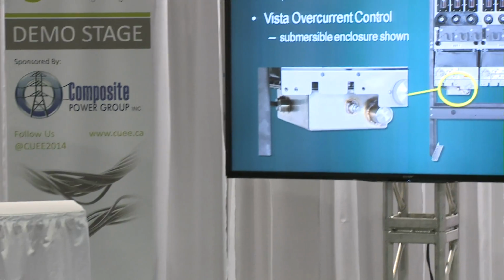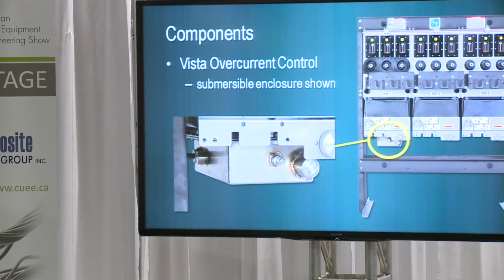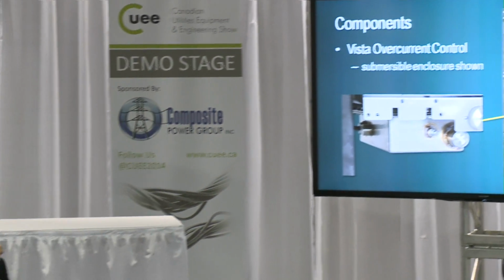If it's a fault interrupter, you get current transformers. It's a self-powered device, so you don't need control power just for the fault interrupter or for the relay. It's powered off the CTs. This is the relay. The relay's in a submersible box. You program the relay with a personal computer, so you basically take the plug off that one port, and then there's a jack, and you plug your computer into that jack, and then you can program the relay.